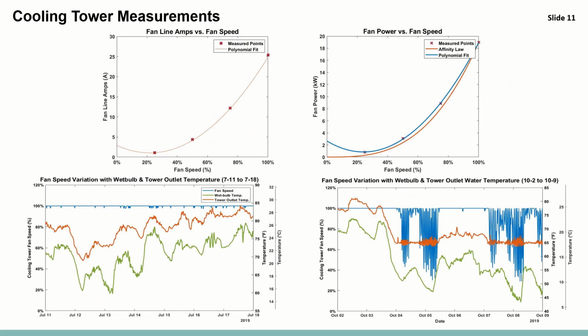Before we get into the cooling tower modeling efforts, I wanted to talk to you about the measurements we took. In lieu of true power measurements over long periods of time, we took three-phase power measurements at 25% fan speed, 50% fan speed, 75% fan speed, and 100% fan speed to create a relationship between the line amps and the fan power and the fan speed. That way we could determine the fan power just based on the amps, and we could take long-term measurements using just a current transducer and a data logger instead of a three-phase power analyzer.